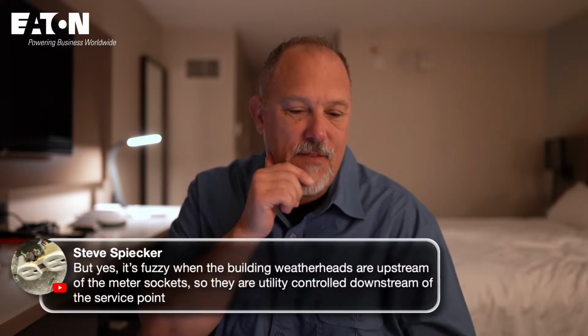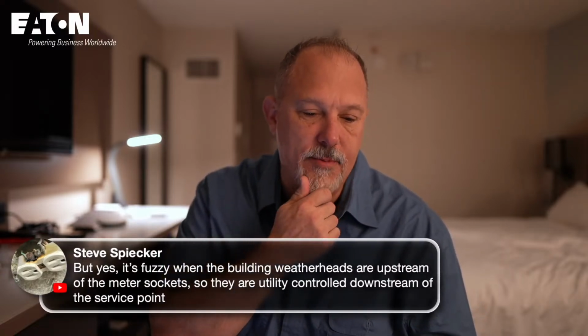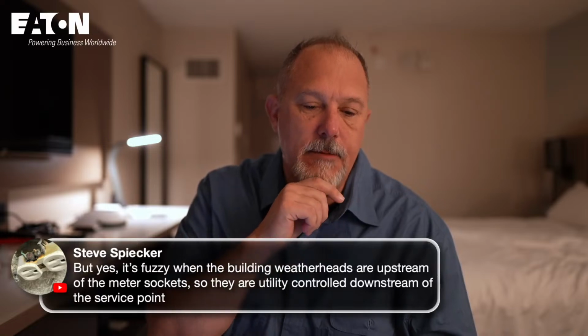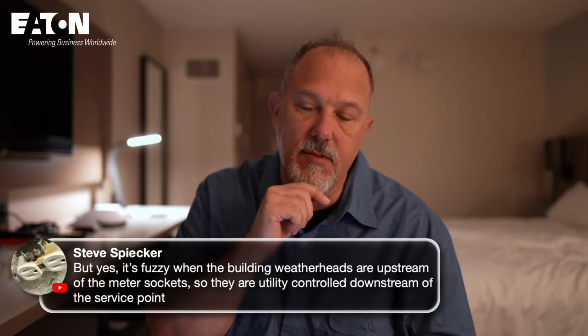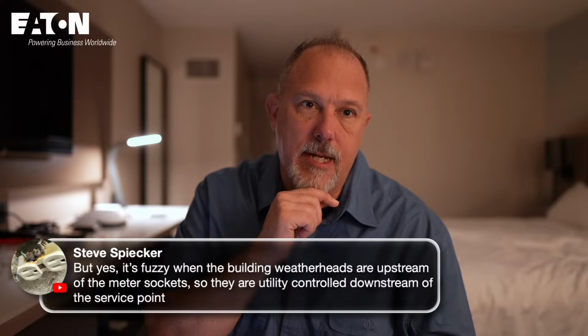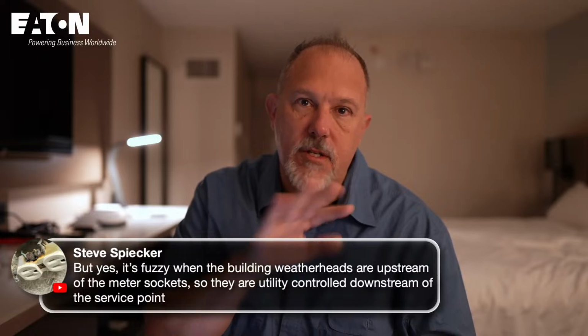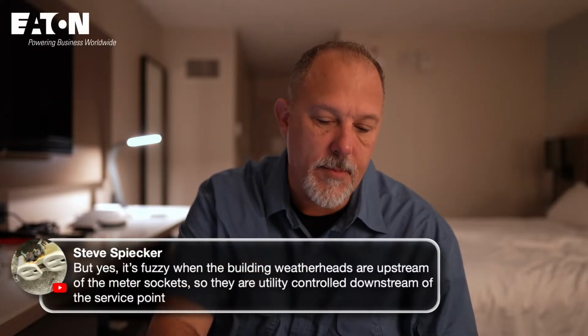But yes, it's fuzzy when the building weatherheads are upstream of the meter sockets, so they are utility controlled downstream of the service point. It is. Services are very complicated, they're very intriguing. But that was another big discussion we had yesterday on 230.4.